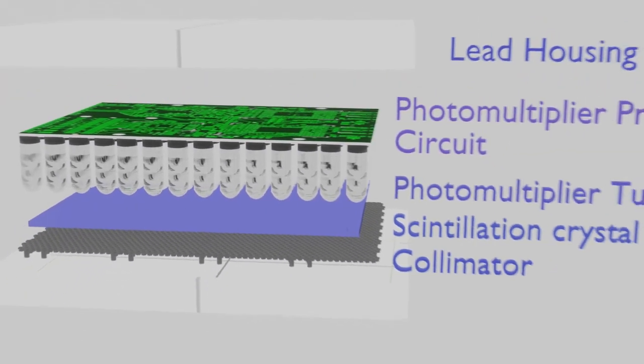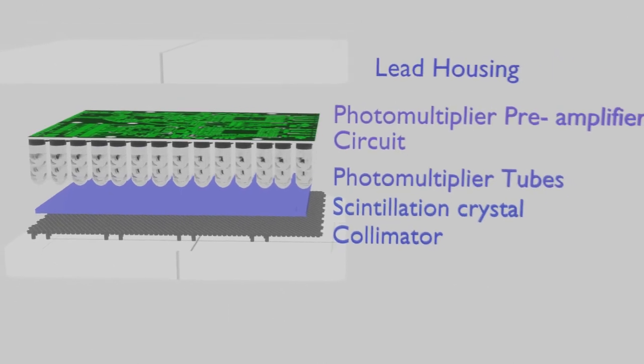The second is that the crystal is viewed by an array of PM tubes, rather than a single PM tube. Signals from the PM tubes are fed to electronic or digital position logic circuits, which determine the XY location of each scintillation event as it occurs by using the weighted average of the PM tube signals.